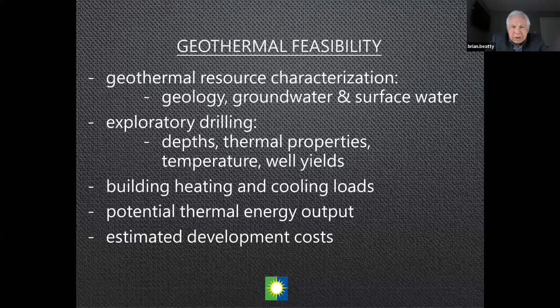From feasibility we move forward to full-scale design, starting again with building energy loads. For geothermal you need hourly loads—unlike conventional systems with boilers and chillers where you may only need the hottest or coldest day of the year, geothermal needs the energy load every hour of the year, over 8,000 hours. You also look at peak loads for each day, week, and month, and the total annual load.